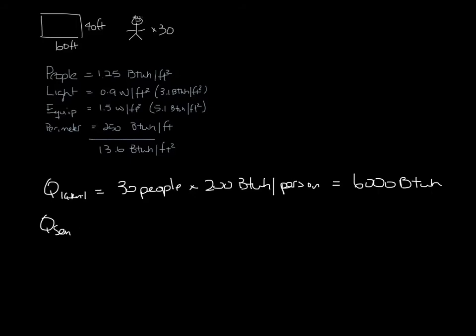Now the sensible load is the 13.6 BTU per square foot times the 60 by 40 space, which gives us 32,640 BTU.